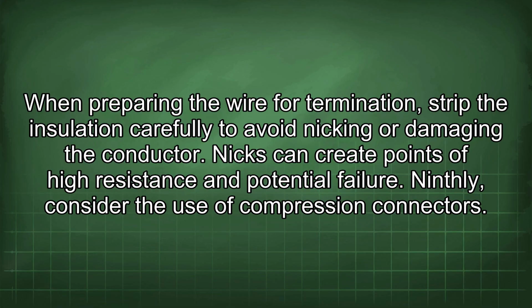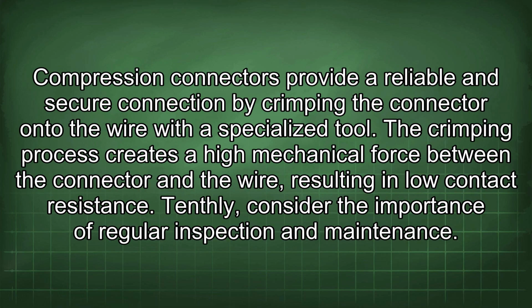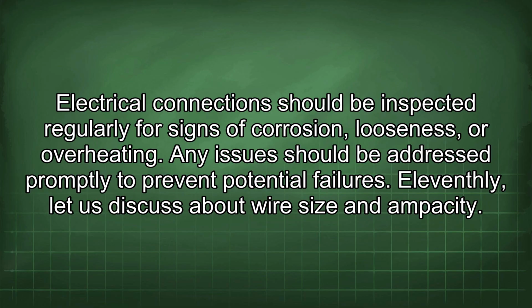Ninthly, consider the use of compression connectors. Compression connectors provide a reliable and secure connection by crimping the connector onto the wire with a specialized tool. The crimping process creates a high mechanical force between the connector and the wire, resulting in low contact resistance. Tenthly, consider the importance of regular inspection and maintenance. Electrical connections should be inspected regularly for signs of corrosion, looseness, or overheating. Any issues should be addressed promptly to prevent potential failures.